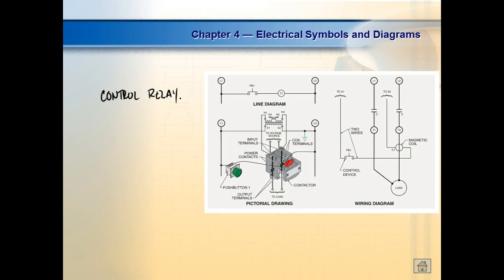So a control relay is a relay whose contacts never leave the control circuit. Normally in motor control, you have two circuits. We're going to deal with just this circuit for a while. We're going to have a control circuit, and then we're going to have a power circuit. Your power circuit is where your high voltage and your energy are going to be. And then we'll have a control circuit. It's going to be a low voltage circuit, and it's doing all the control, right? Relatively low voltage.